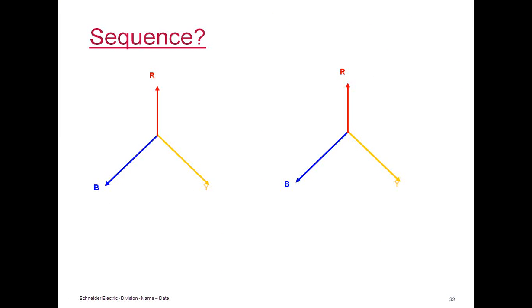So one of the key things in harmonics is the sequence. Sequence in harmonics is critical for us to understand how exactly the harmonics will affect various equipment. Sequence plays a critical role in terms of how a machine will behave or misbehave with harmonics in the system.